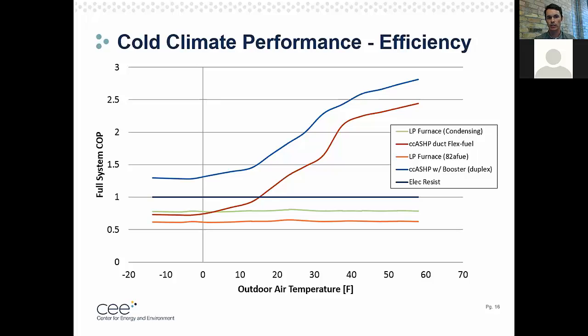I'll start by walking through what this blue line means, which is our all-electric system. At these higher temperatures, all the way down to 30 degrees, this system operates above 2 COP, so above 200% efficient. It's pulling heat from the outside and delivering it to the inside of the home at 200% efficiency because it's moving that heat around rather than creating it. As it gets colder and colder, the efficiency of that system goes down, but even as cold as -10 degrees, that system is still operating at above 100% efficiency. What's happening with this line and curve is that the electric booster backup I talked about with that ducted system is coming on to meet part of the heating load of that home.